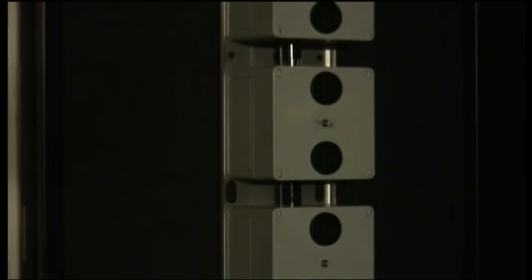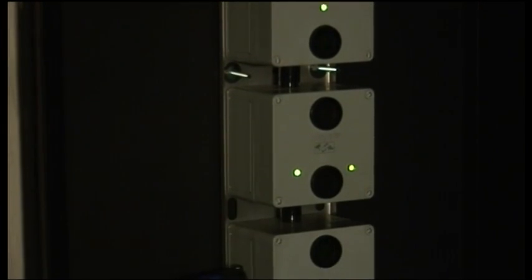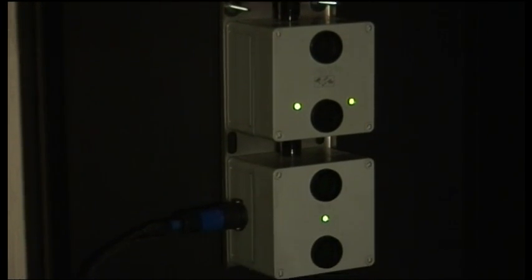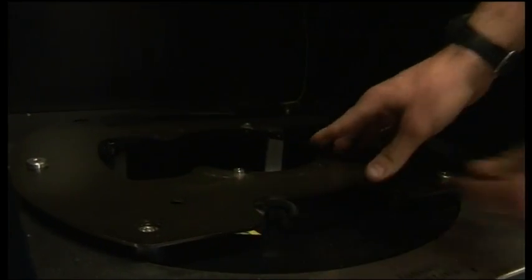Whilst the MARMS Photometric Bench is an enhanced unit, which measures photometric performance on a 1 degree by 1 degree basis, as with the MARMS mobile trailer, it utilises a 12-sensor array as specified by ICAO Annex 14, and provides the facility to store and review results.